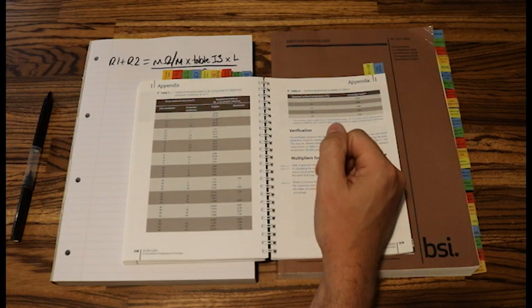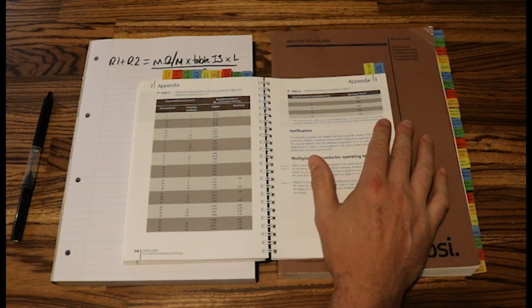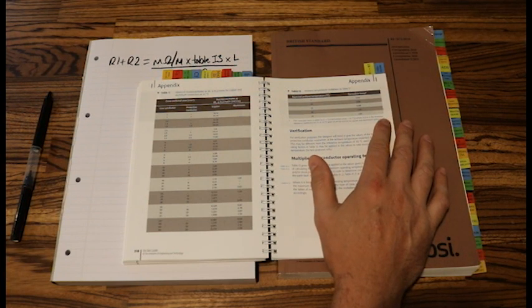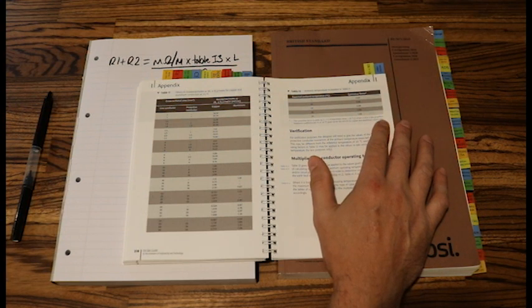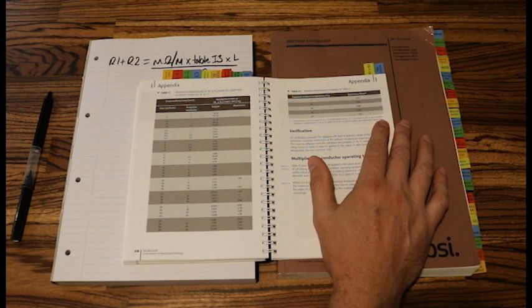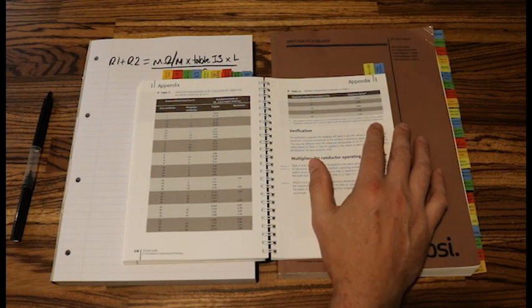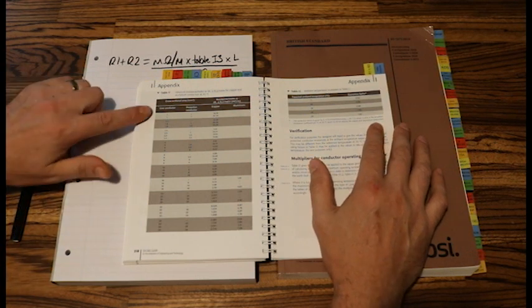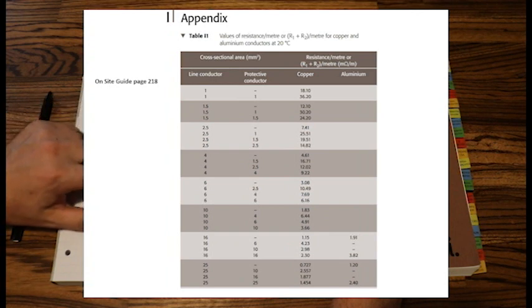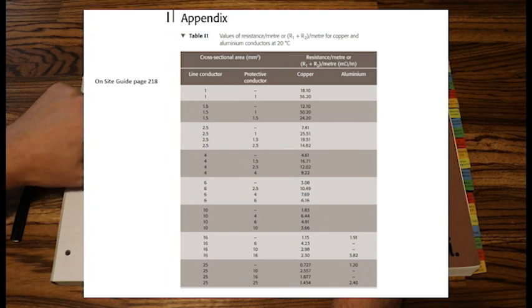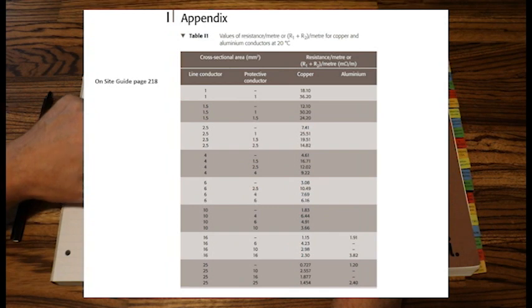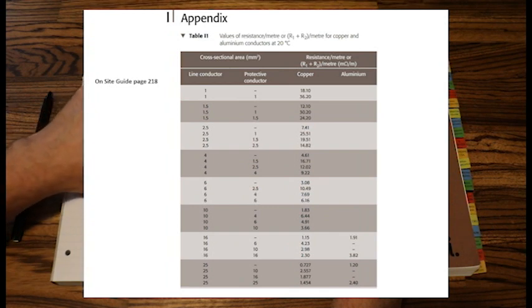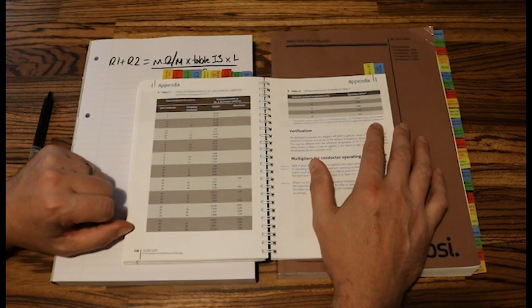So I've worked out I need 6mm live cable. I'm going to be using 6mm live cable. To size the earth cable we start by using the same size earth as the live cable. So in our first column as you can see it says line conductor size. The second column says protective conductor size. And then this third column will give me my resistance per metre, this milliohms per metre value.